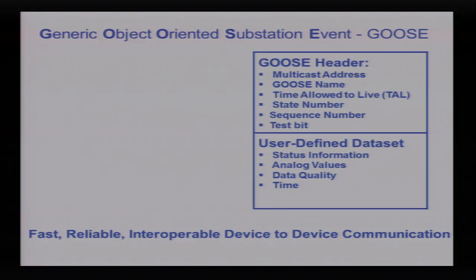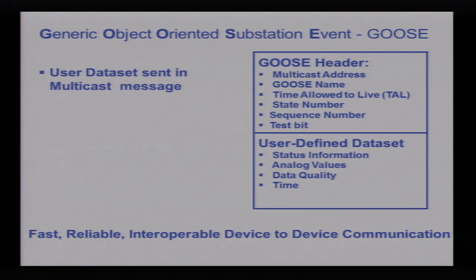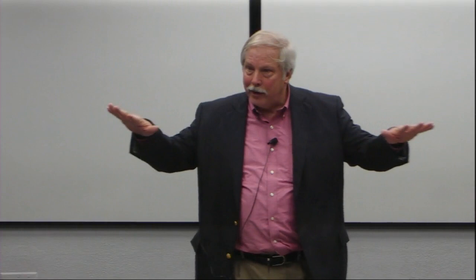The name for this is the Generic Object-Oriented Substation Event, or GOOSE. GOOSE is a publisher-subscriber message. It's a multicast—multicast is a special feature of Ethernet. An Ethernet address has 48 bits in the address space; if bit 8 of that address is set to 1, it identifies that message as a multicast message. So what I'm doing right now is called broadcast—I'm sending a message to everybody in this room. Multicast says this message is only for people in the third row back.